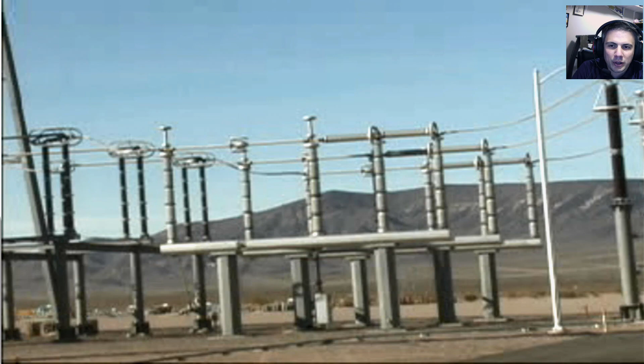So now it gets so hot that it liquefies the copper, and it explodes outwards at all angles until it finds a way out of the enclosure, and then it becomes a straight path. If you're a worker with the door open at the time, that straight path is coming right into your face, right into your body, and it's enough pressure that it will send a full-grown person flying across the room. There's a lot of power there.